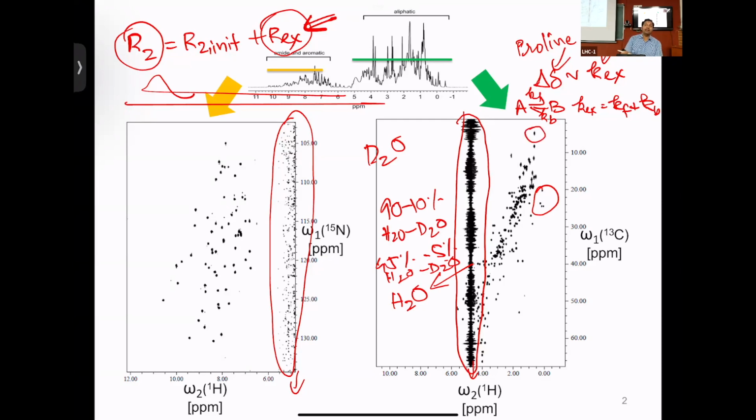Then you may ask, why is it coming at all? That's because when you execute the pulse program, there'll be some amount of relaxation that happens before the last 90-degree pulse. So after the water relaxes, you'll still be able to see it. We end up doing some techniques to suppress water, as you have effectively suppressed here, but not always it happens.